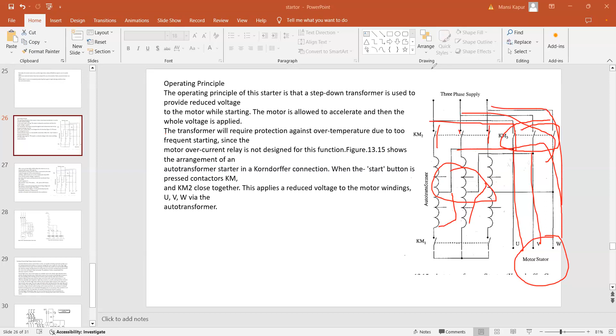The motor is allowed to accelerate and then full voltage is applied. First, you will accelerate the motor using this voltage, which you are tapping from your auto transformer. Then you are going to close the KM3 and apply the full voltage, right? The transformer will require protection against over temperature. So for this transformer, we require protection against over temperature.